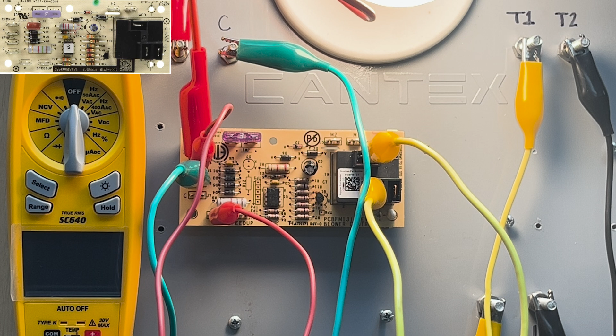The M2 is a park terminal, M1 is a park terminal. You have 3 speeds typically on these motors - high, medium, and low. It's recommended that you run everything on medium speed to get 400 CFM per ton. So the low speed and high speed that I'm not using, I would just push them on there so they're not just sitting loose in the cabinet - I want to safe those off.